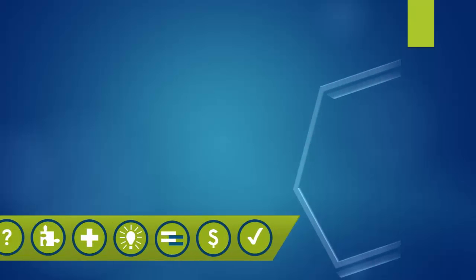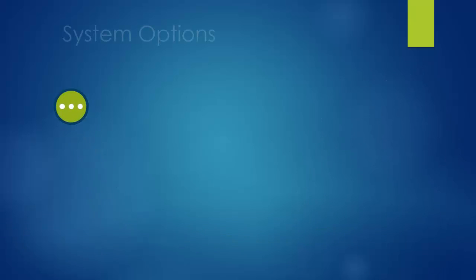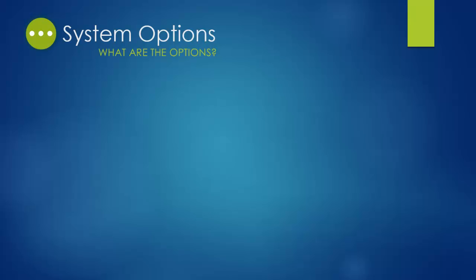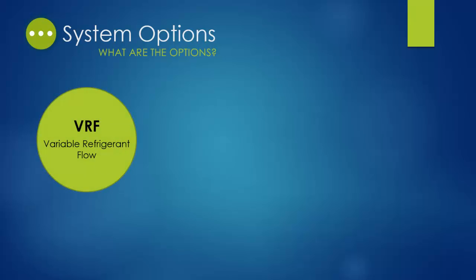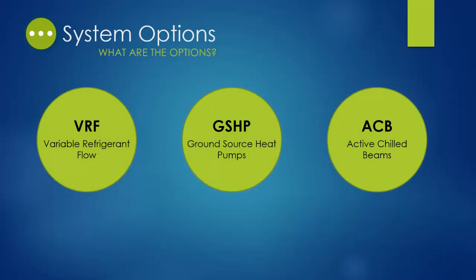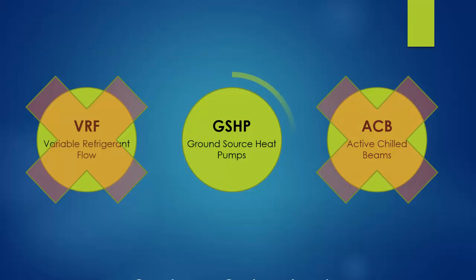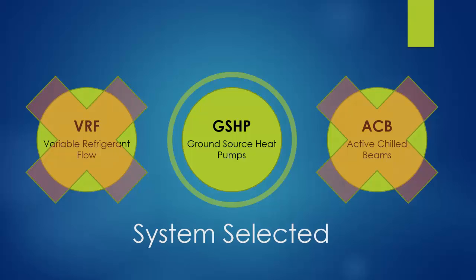After considering the goals for the project, the following systems were analyzed in detail: variable refrigerant flow, ground source heat pumps, and active chilled beams. To evaluate the 3 systems, a decision matrix was formed and points were given to each system based on the project goals, owner requirements, and building design parameters. After this comparison, the ground source heat pump system was selected as the HVAC system for this building.